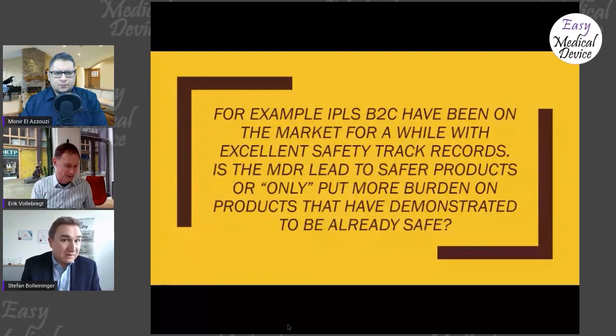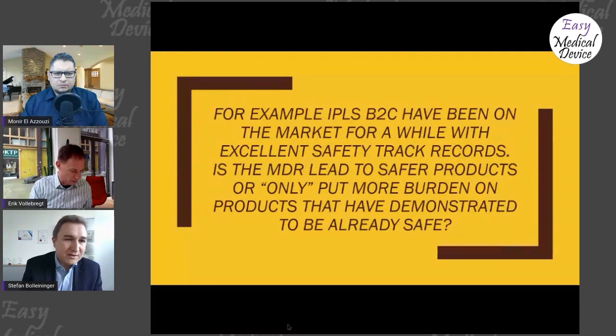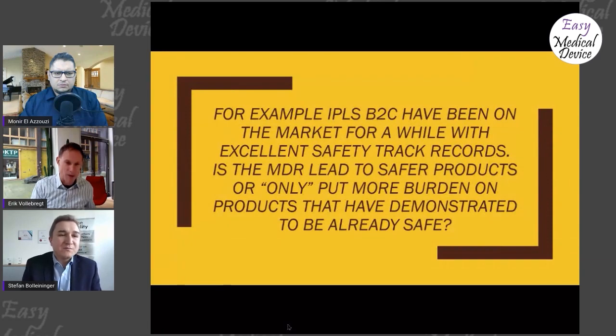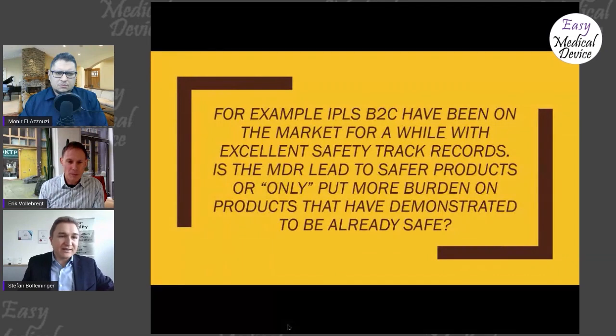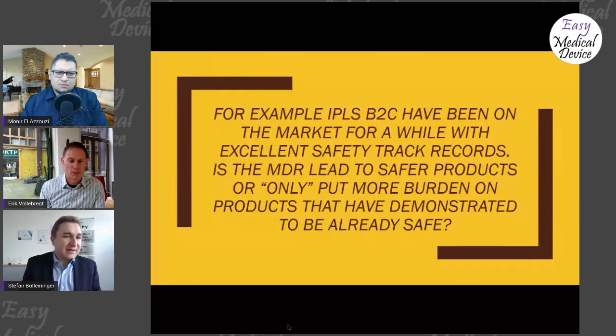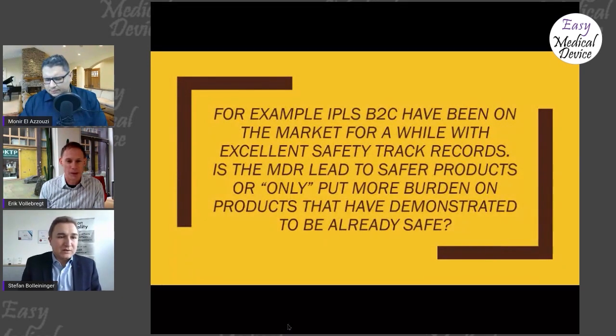And safe. Yes. Yeah, but there is one thing. I had a very long discussion with one notified body, and there are the principles of equivalent safety. So if you have a medical device performing the same action, then you also need to look at those standards and their limits. Maybe you have a limit, maybe not. The common specification doesn't tell you there's a limit, but maybe one of the standards, say electrical standards or something like that, gives you a specific limit that you should not exceed, like photoelectronics or human light exposure. Yeah, okay. But it's not easy to answer that completely in general, because that's not possible for any device.